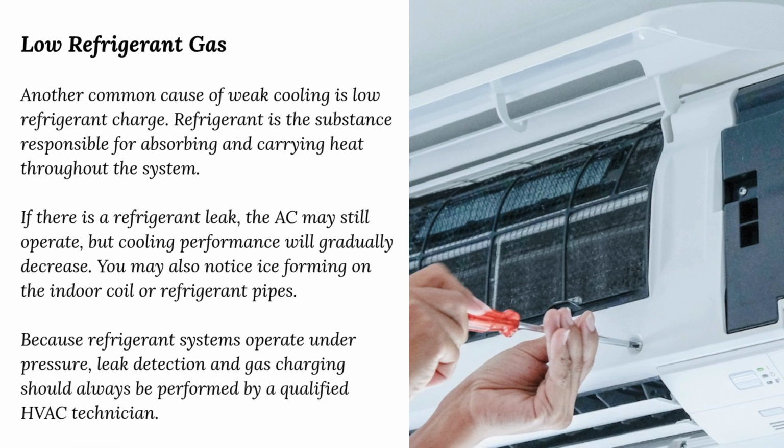Low refrigerant gas. Another common cause of weak cooling is low refrigerant charge. Refrigerant is the substance responsible for absorbing and carrying heat throughout the system. If there is a refrigerant leak, the AC may still operate, but cooling performance will gradually decrease. You may also notice ice forming on the indoor coil or refrigerant pipes. Because refrigerant systems operate under pressure, leak detection and gas charging should always be performed by a qualified HVAC technician.